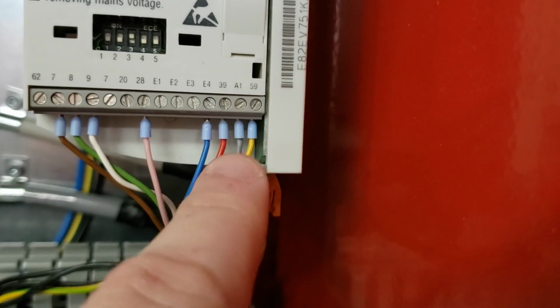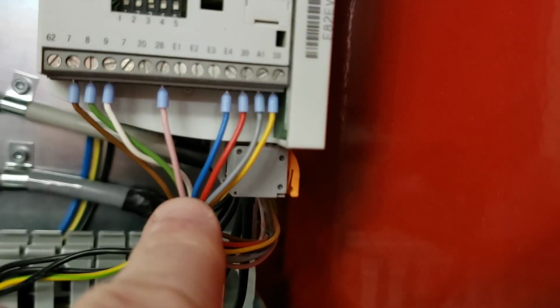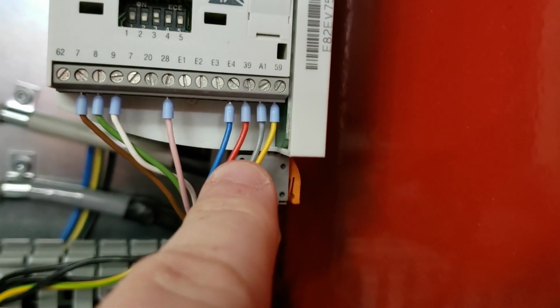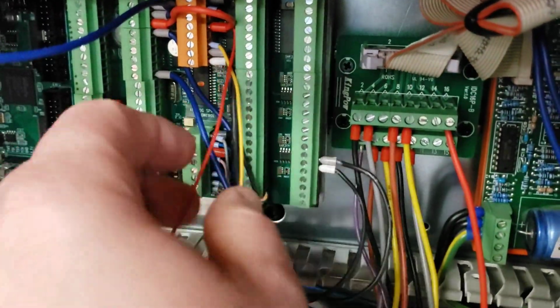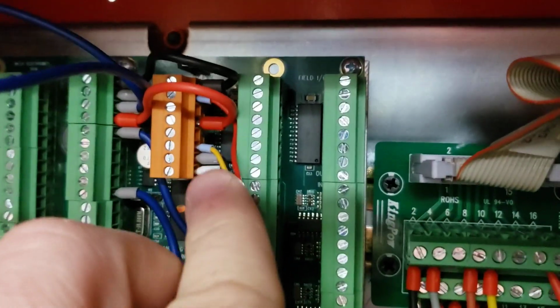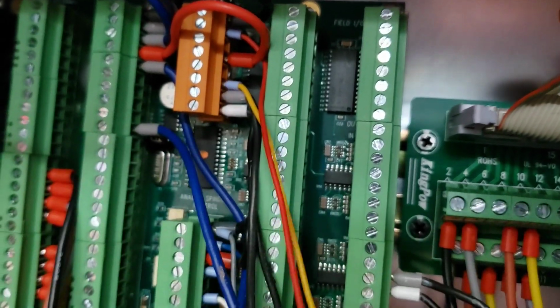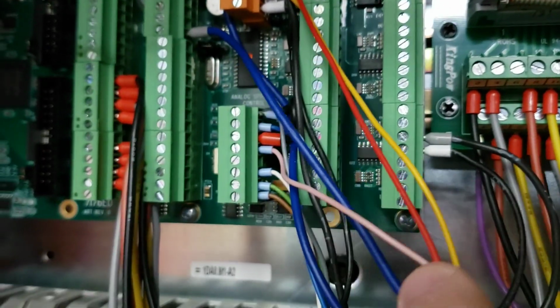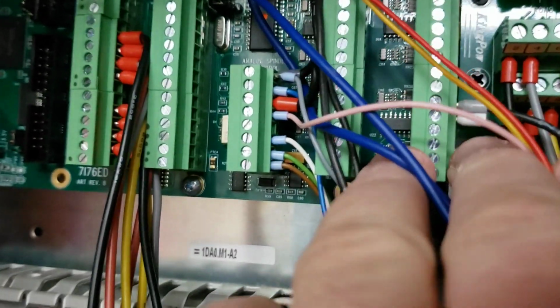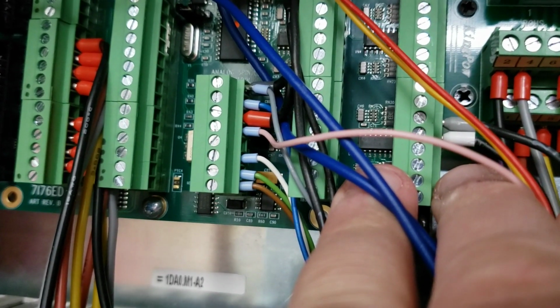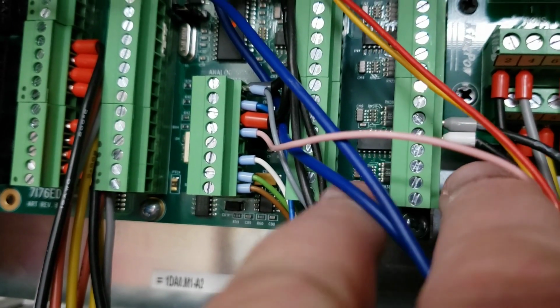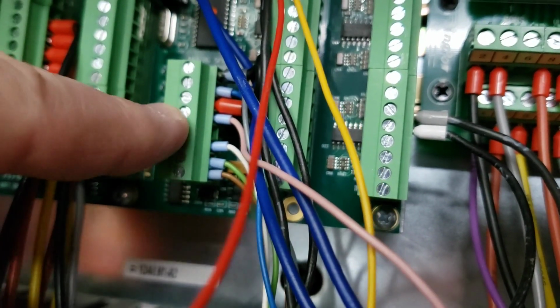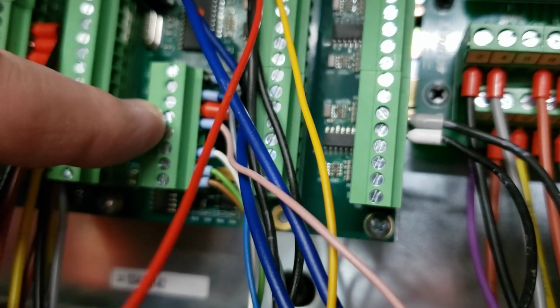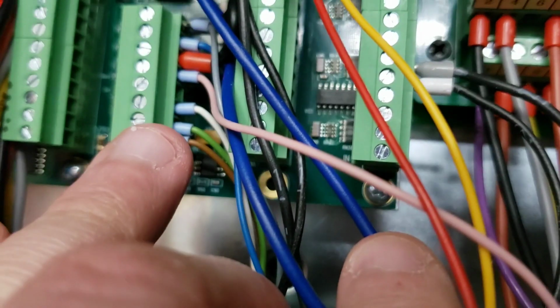59 is a 24-volt input, and then the A1 is a 24-volt output to an enable signal. The way I have it set up right now is I've got 24-volt and the red common coming out of the field I/O block here. And then, let's see if I can move this stuff out of the way here, I've got a 24-volt gray return wire coming into terminal number 8. And then I've got the blue wire in terminal 7. I've got a jumper from 8 to 6, which ties into the enable. So this is the direction pin. This is the enable pin. And then again, I've got the potentiometer stuff at the bottom.